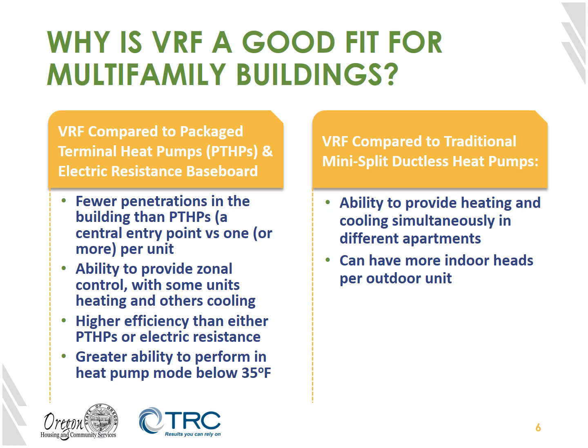So why is a VRF system a good fit for multifamily buildings? For one, let's compare this to upgrading to package terminal heat pumps. A package terminal heat pump is usually the large block unit that would go through an exterior wall of the building, really often under a window. Just imagine the size of that penetration if you're upgrading from electric resistance to package terminal heat pumps. You're needing to put a large penetration in every unit or every zone that you're intending to heat and cool throughout the building. So it's quite a bit of additional disruption to the exterior to put in package terminal heat pumps.